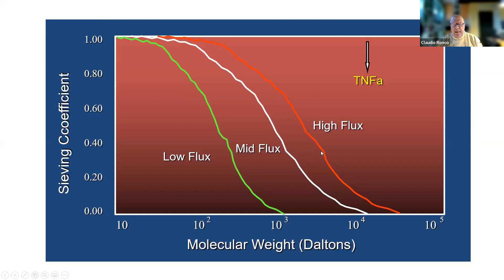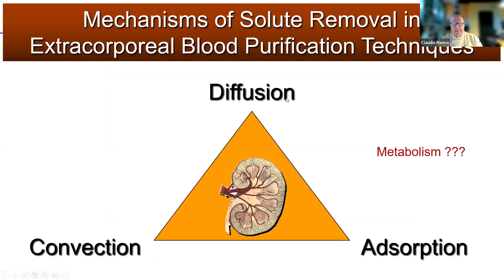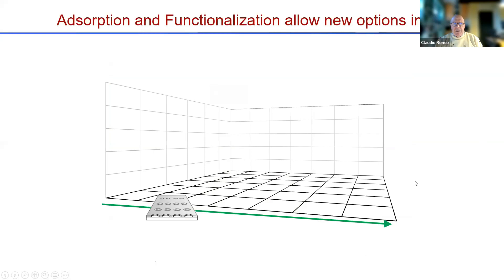Different membranes have been created with different sieving properties, trying to mimic the sieving coefficient curve of the human glomerulus. But still, we are far from that. In fact, some molecules that are important for acute and chronic kidney disease are retained in the body. However, we discovered some years ago that the membrane can be an active component and can indeed be utilized to adsorb some substances. This was one of the first publications we did, showing that TNF-alpha could be adsorbed on the internal surface of the membrane. So the mechanisms we use today are basically diffusion, convection, and adsorption, waiting for possible bio-artificial organs that include metabolism.